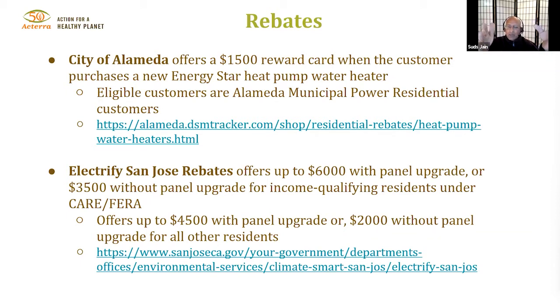The issue with panel upgrades is that if you're going to install one of the 240 volt, 30 amp water heaters, you may not have enough capacity in your panel to run it. In that case you'd want to upgrade, since some people have 60 amp panels, some have 100 amp panels. I have a 200 amp panel, which allows me to use almost 50 kilowatts of power, a tremendous amount. But if you have one of the smaller panels and you're trying to electrify your home, it's probably recommended that you upgrade to a 200 amp panel.